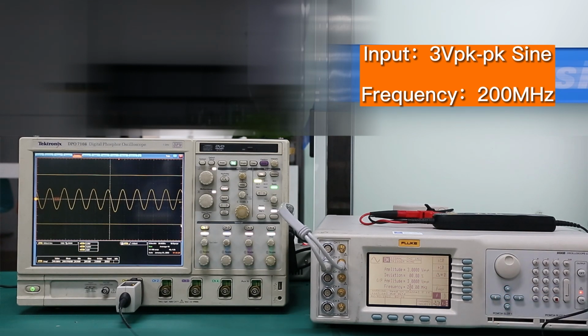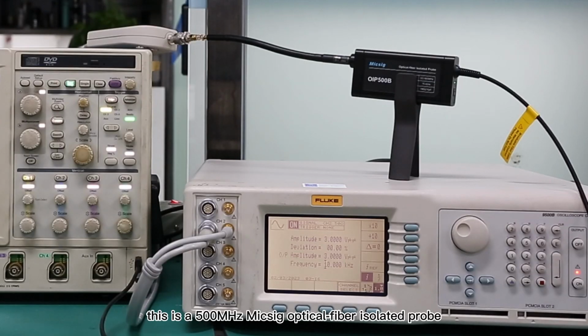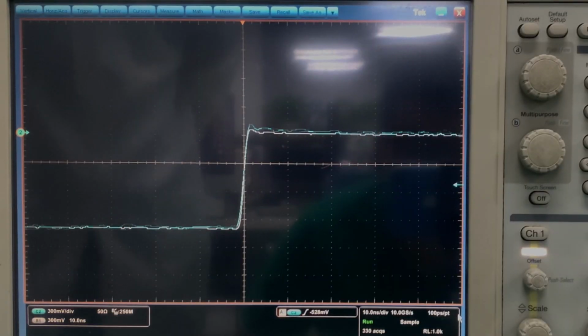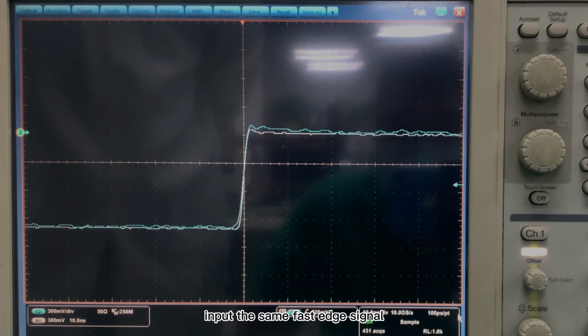We can see, as the signal frequency changes, the output amplitude of the differential probe fluctuates, with no accuracy. Therefore, no matter how high the differential probe's bandwidth is, it is useless for measurement. This is a 500 MHz Micsig optical fiber isolated probe. Input the same fast edge signal.